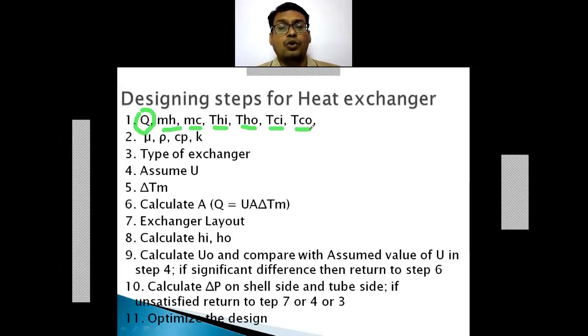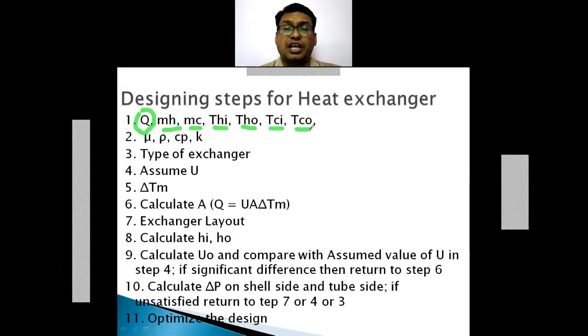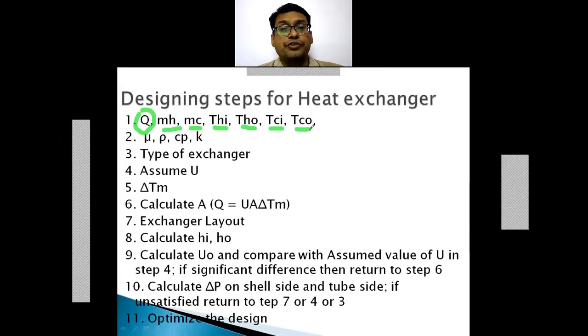The next step is to collect the different physical properties: viscosity, density, specific heat, and thermal conductivity for the hot fluid and the cold fluid, as well as the thermal conductivity of the separating metal wall. These physical properties should be evaluated at the average temperature — for the hot fluid, the average of the inlet temperature T_H_in and the outlet temperature T_H_out.